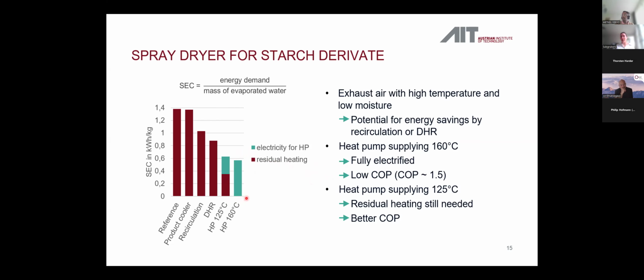Maybe a more economic configuration would be a heat pump supplying just 125 degrees. Then there is still residual heating needed in the drying process, which is then probably natural gas. But the COP, of course, is a lot better, and the electricity consumption is smaller. And the specific energy consumption is nearly the same as for the high temperature heat pump with 160 degrees.